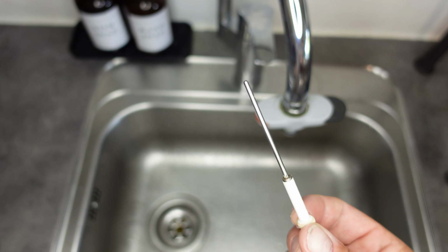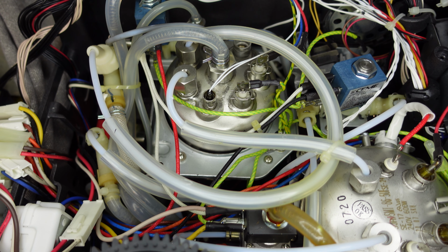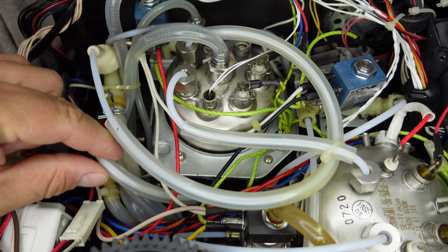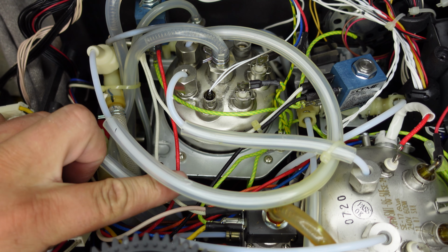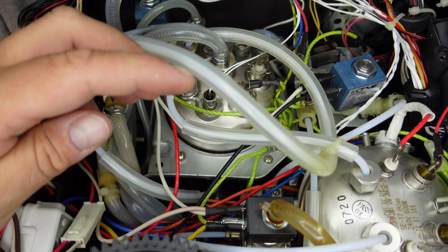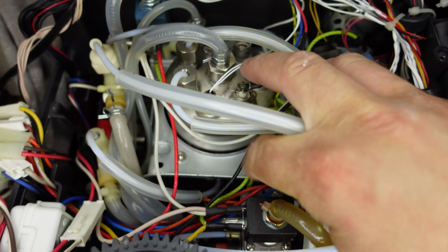Earlier, I looked into the boiler with a flashlight to check the water level and only the heating element was covered. That tells me the boiler isn't filling up, and I suspect the hose is clogged with limescale. Since the pump has been running constantly since startup, the next step is to check the hose.